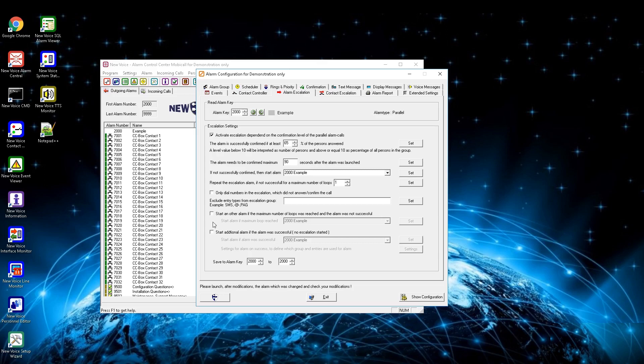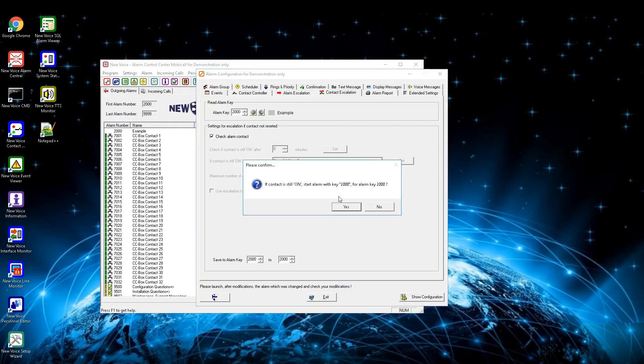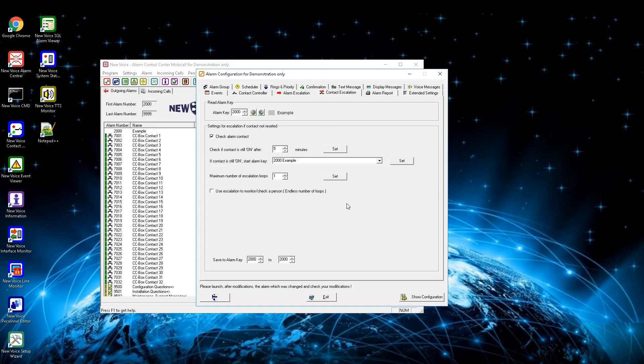The last option in escalation is to start an additional alarm if the alarm was successful without escalation. With the checkbox check alarm contact, MobiCall will check the contact from this alarm number to see if it is still on. Activate the box to check if the alarm contact is still on — a time in minutes needs to be defined. If the contact is still on after the predefined time, a chosen alarm will be started, defined via the drop-down menu. The menu below sets the amount of loops for this escalation, and the last checkbox monitors a person with an endless number of loops.